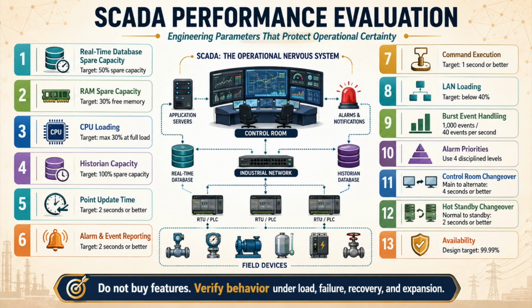What point count was tested? What scan rate was tested? What alarm load was tested? What historian write rate was tested? What client count was tested? What CPU margin remained? What RAM margin remained? What LAN loading occurred? What failover time was proven? What recovery philosophy was used? What command response was measured? What timestamp accuracy was verified? What architecture was actually tested?